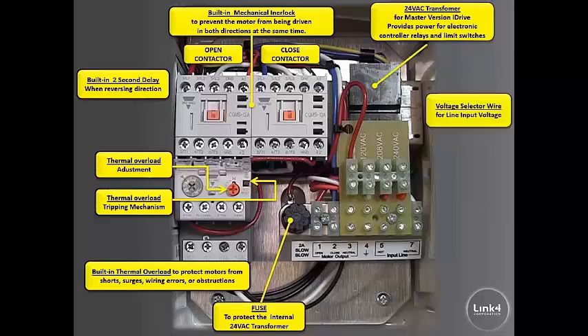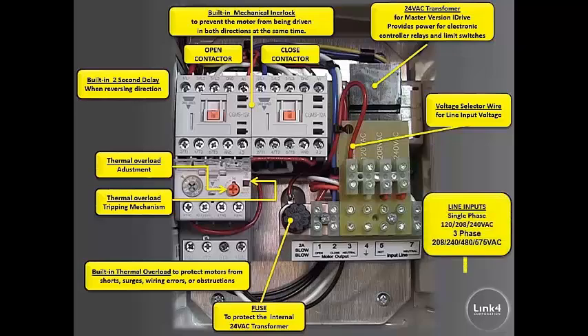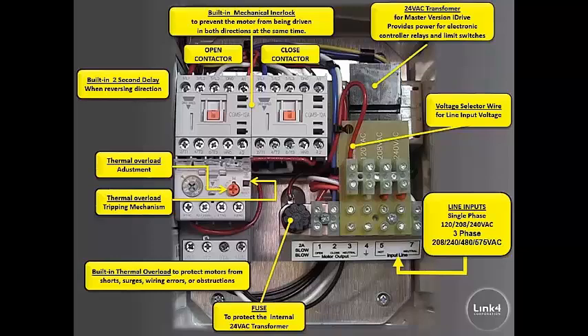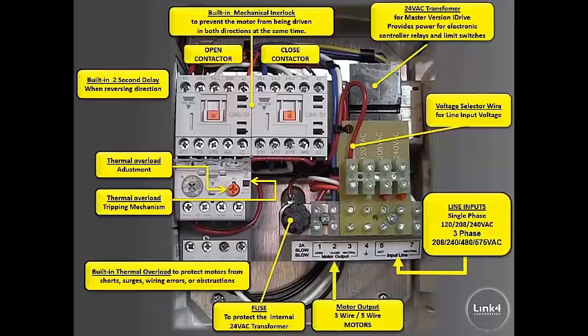You have a voltage selector wire for line input voltage, line inputs for single phase 120, 208, and 240, and three phase for 208, 240, 480, and 575. Also, motor outputs for three wire and five wire motors.